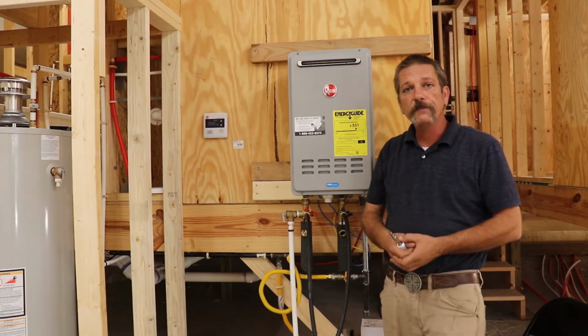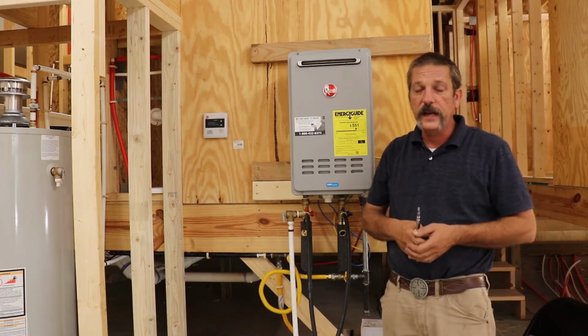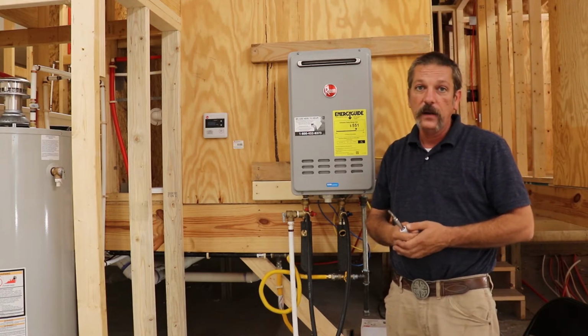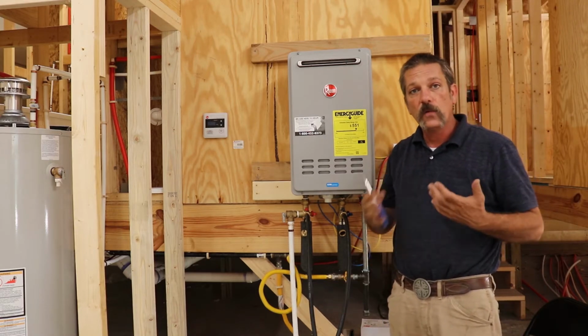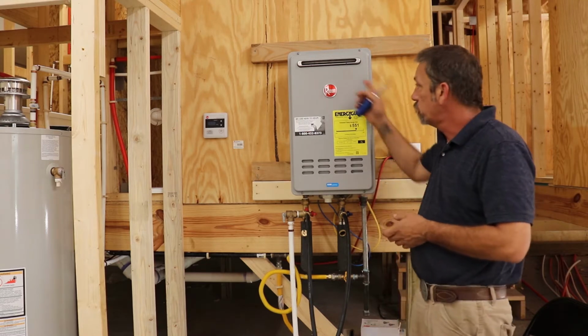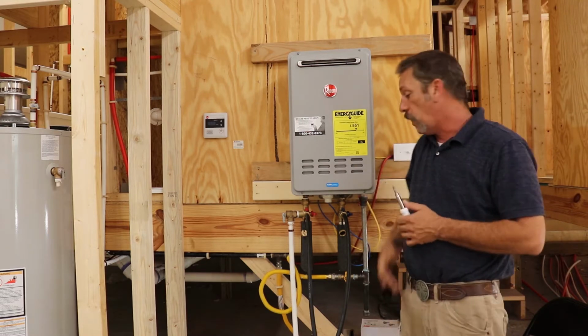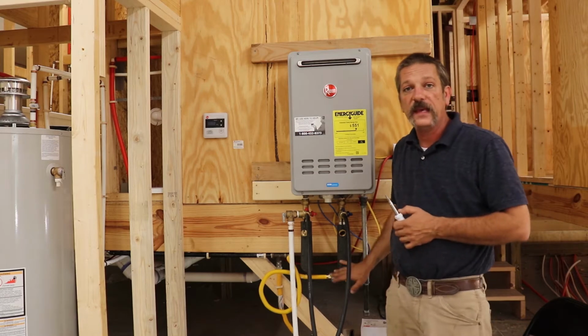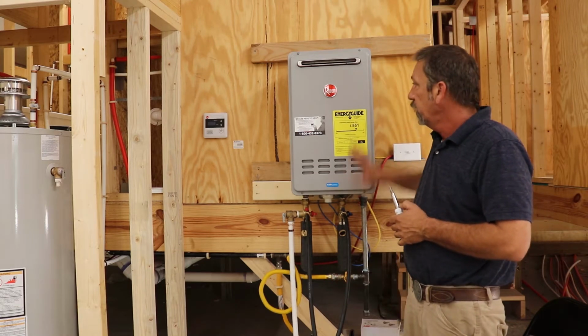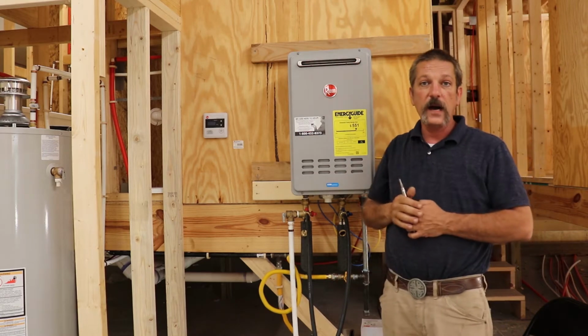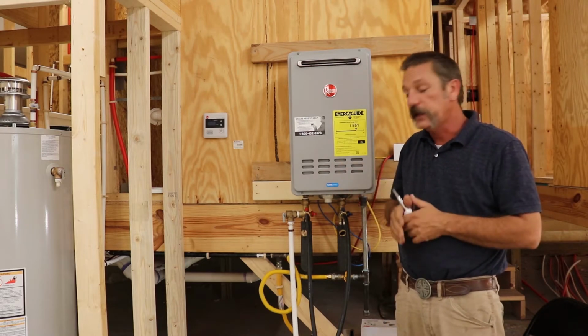We have our pump running. Now, descaling a water heater is going to take an hour. You're going to want to let this pump sit there and run for an hour to make sure it cleans all this stuff out. If you left the power on and the gas on, this is probably going to kick on in a low fire mode, and that's perfectly fine.